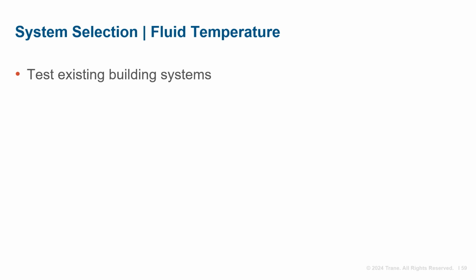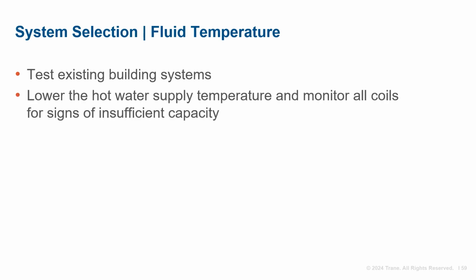With that in mind, one method to determine the optimal hot water temperature is to test the building systems. Lower the hot water supply temperature and identify the temperature where coils start to lose discharge air or space temperature control. It's common for systems designed for 180 degrees Fahrenheit to function with 160 or in some cases hot water supply temperatures in the 140s.